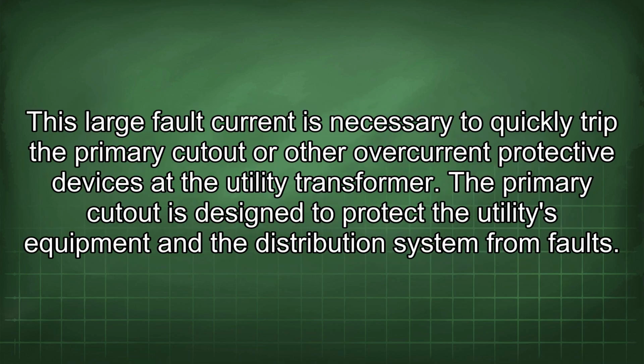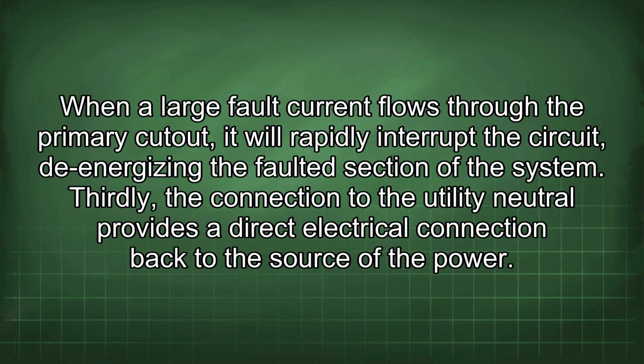This large fault current is necessary to quickly trip the primary cutout or other overcurrent protective devices at the utility transformer. The primary cutout is designed to protect the utility's equipment and the distribution system from faults. When a large fault current flows through the primary cutout, it will rapidly interrupt the circuit, de-energizing the faulted section of the system.